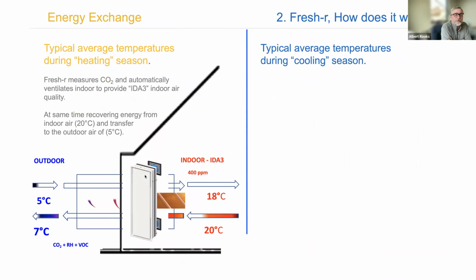Super interesting system. So the energy exchange is pretty much the way we're used to. It's running demand control, and the demand is driven by CO2, RH, or VOC. A case of VOC is, in high performance HRVs where there's no bath fan or kitchen fan, when I go in and burn a pizza because I just suck at cooking pizzas, which is true, I create a big cloud of blue smoke. Normally I'd have to walk over, hit a button and turn on a range hood or the ventilation system, and I push my button and go into boost mode. Because this thing is actually measuring VOCs with those laser sensors, it sees the high VOCs that I'm producing in the kitchen from its return flow. And it doesn't see high VOC outside, so it'll increase the fan rate. It'll put it in boost and run boost as long as there's a high concentration of VOC, and then it'll back it off because it's got a little set of logics. I've never seen a device do that before.